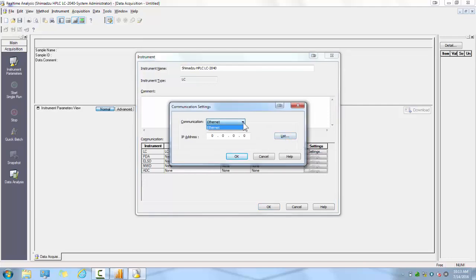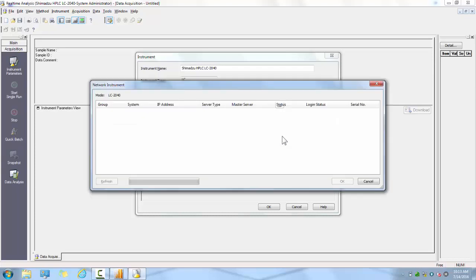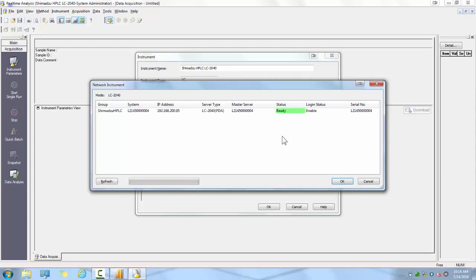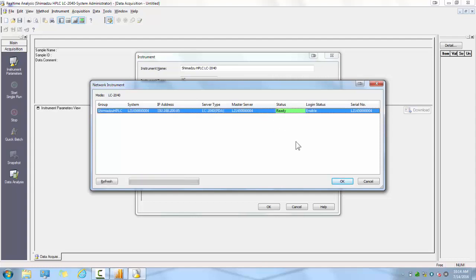If your system has an option for communicating via RS-232, you will see it as an option in the drop-down menu. In the case of the i-Series, the only option is Ethernet. You can manually input your IP address here, or you can search for available IP addresses by clicking List. We recommend using the List feature, as it also acts as confirmation that your IP communication settings are correct if it shows up in the list. Once you see your system identified in the list, click on it to select it and then click OK.